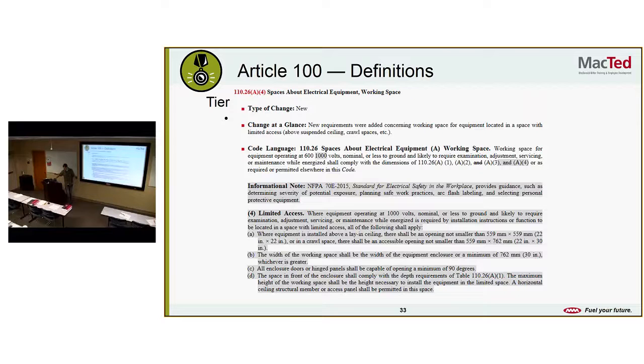Looks like where equipment operating 1,000 volts nominal or less to ground and likely to require, so there's a list of stuff here. Where equipment is installed above a lay-in ceiling, there should be an opening not smaller than 22 by 22, or in a crawl space, there should be an accessible opening not smaller than 22 by 30. So that'd be kind of nice. Hard lids, stuff like that. They'd shove duct heaters. So now there's a requirement for that. So if you go on any jobs and you find that there's not adequate access, you don't have a 22 by 22 in that hard lid, there's the code to cite. You just cut yourself a hole. Or better yet, you have them cut it. They didn't do it. So it's a good one to keep in mind right there.